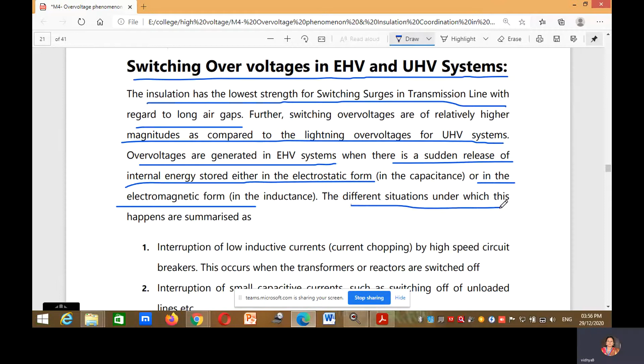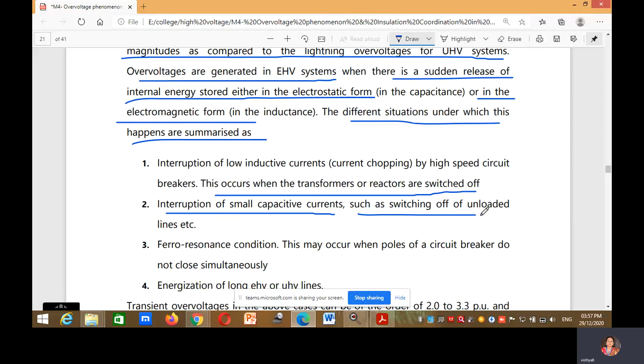They are saying that overvoltages are generated in extra high voltage system when there is a sudden release of internal energy stored either in the form of electrostatic or electromagnetic. The different situations under which this happens are summarized as interruption of low inductive currents by high-speed circuit breakers. This occurs when the transformer or reactors are switched off. Interruption of small capacitive currents such as switching off of unloaded lines, etc.